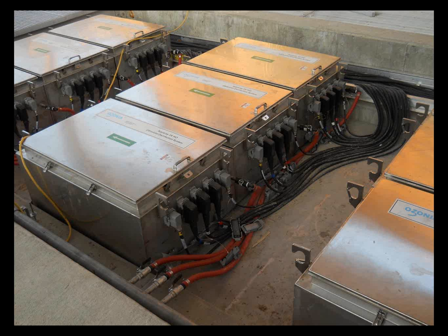This is the modules closed. You can see the air lines that are hooked to it, again, for the cleaning. You can also see all the electrical plugs. Another great thing about this, there's no unwiring. There's nothing to unbolt or unscrew. It's just quick connect couplers on the air lines, quick connect couplers on the plugs. You run a bar through the latches, through the clamps along the top of the thing, and pick up one module at a time or pick up all three for maintenance or cleaning.